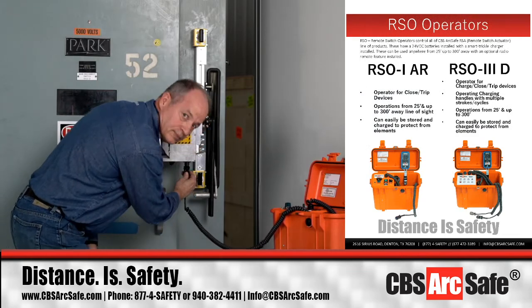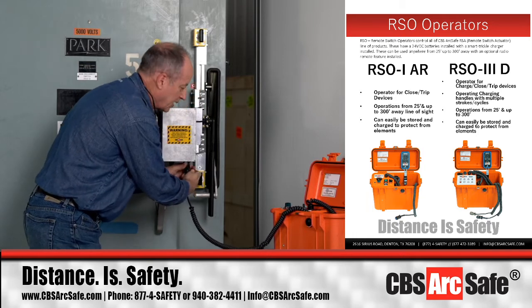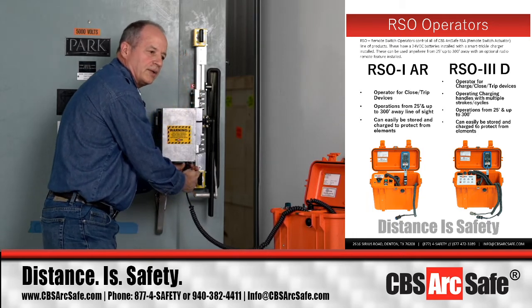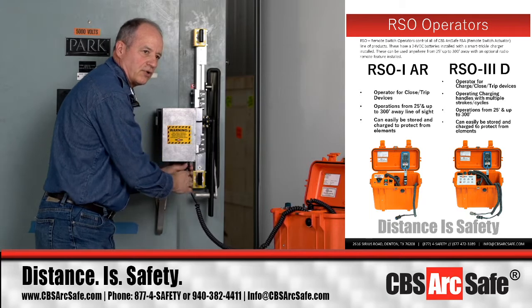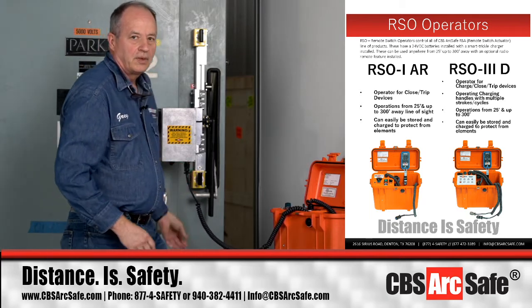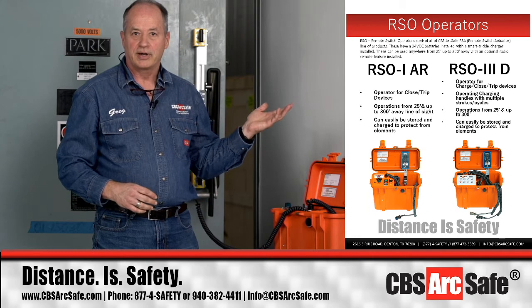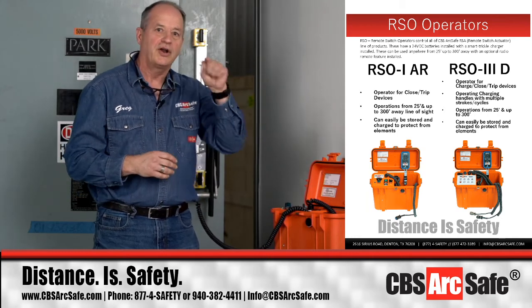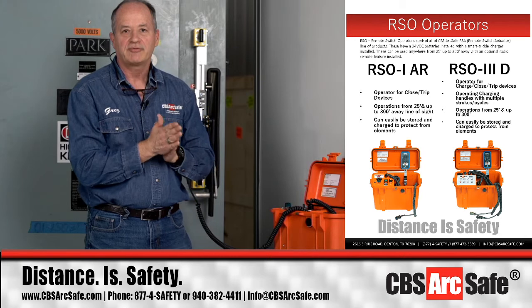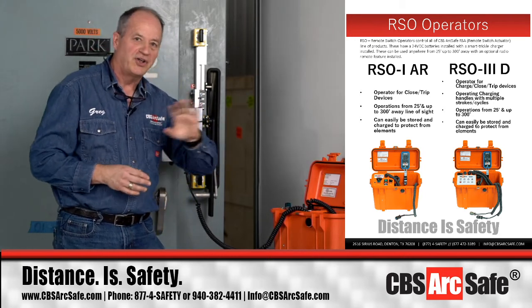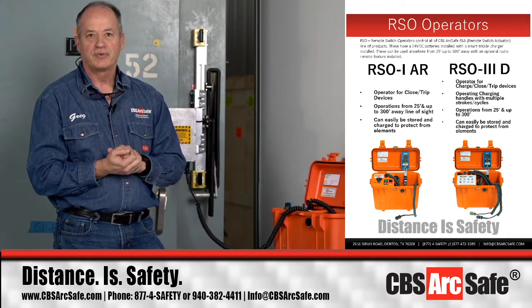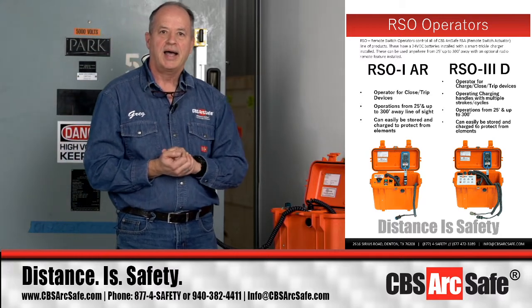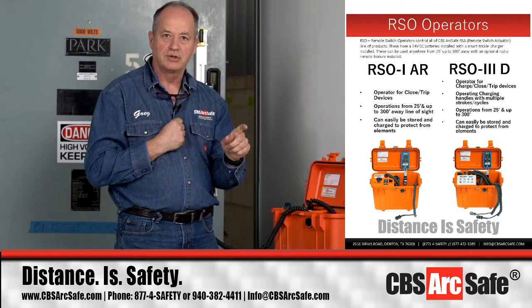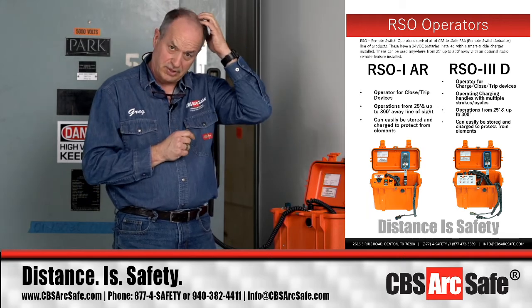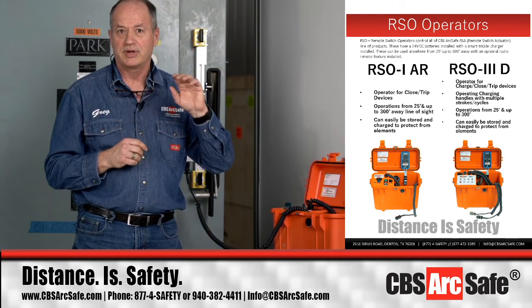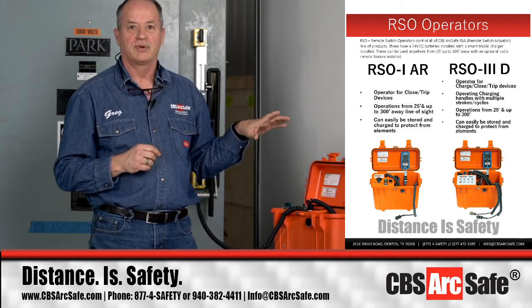Greg, just talk a little bit about the differences in RSO3 and RSO1. When we first started doing this over 11 years ago, somebody said, I need to operate a breaker control switch or a push button, that's an on-off function. After making simple actuators for on-off functionality, about three or four months into the process, somebody said, I have to have something that will charge, close, and trip a breaker. We were like, gee whiz, we don't want to change anything we've already done, and we don't want to sell somebody more functionality than what they need.